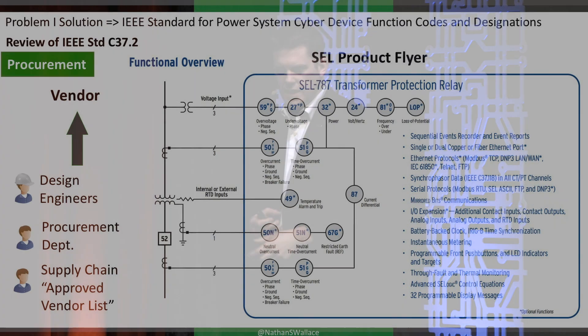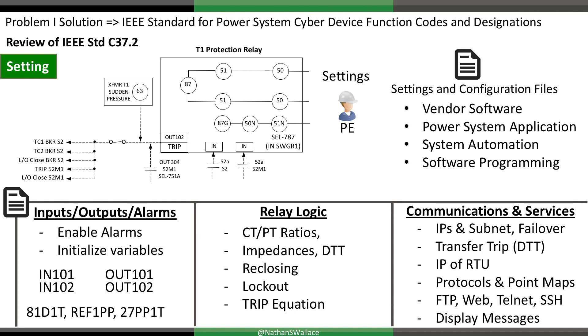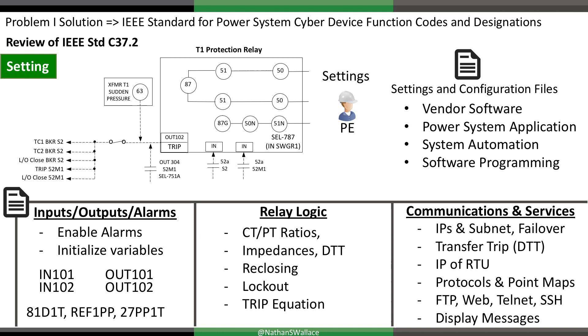So that's the design for the procurement guys. Vendors can come out and say, my device does this — these are the functions that this black box can perform. There are numbers and syntax around it, a universally understood language for what the device is capable of doing. For settings: the settings engineer takes this operational one-line, and looking at the different categories on the drawing, the settings engineer today in power systems is actually setting cybersecurity-type metrics or settings in these relays — inputs, outputs, alarms, protection relay word bits, and the trip equation.